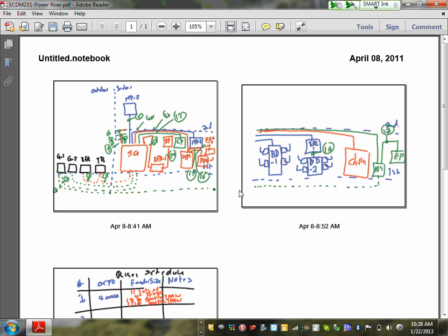Generator one comes up to speed and voltage. The system will close that breaker onto the bus. Now it waits for the second generator to get up to voltage and speed, and when it gets into sync with this one, in other words, the waveforms of both of them are tracking, it'll close the second generator onto that bus. So now we're totally on generator power at that point.